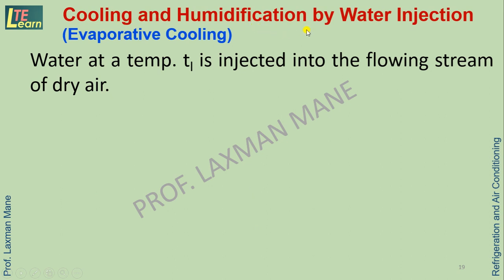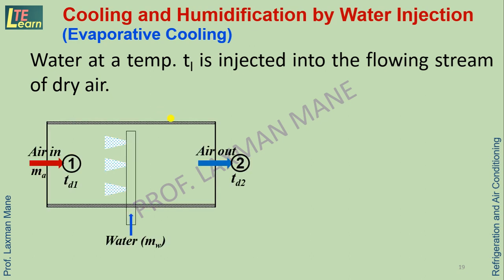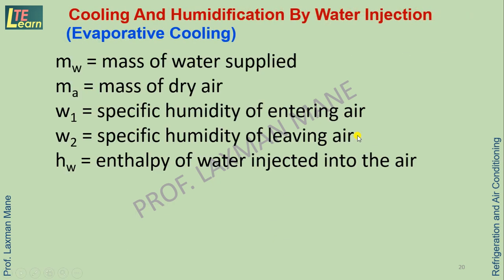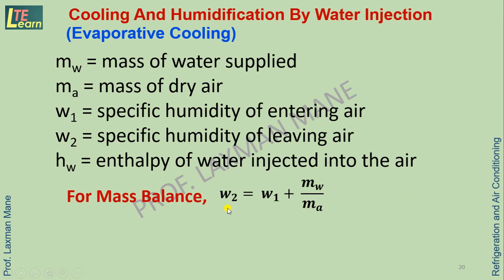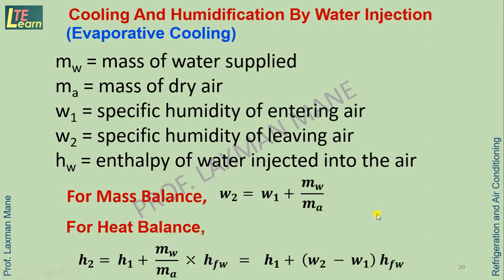The process of cooling and humidification by water injection is called evaporative cooling, where water at temperature Tl is injected into the flowing stream of dry air. The mass balance equation gives: W2 = W1 + (Mw / Ma), where Mw is the mass of water supplied, Ma is the mass of dry air, W1 and W2 are specific humidity at entering and leaving, and hfw is the enthalpy of water injected. The heat balance equation gives: H2 = H1 + (Mw / Ma) × hfw, which can also be written as H2 = H1 + (W2 − W1) × hfw.